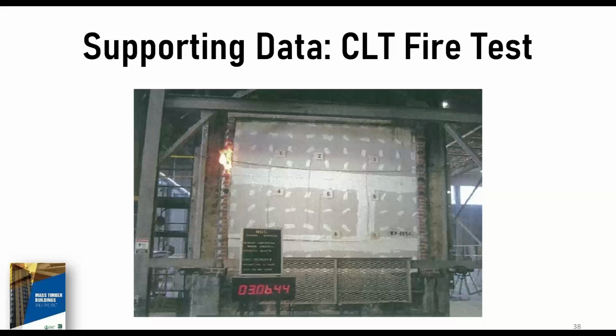The first is a penetration, flame front penetration of the assembly. You can see in our picture here we have a little flame licking out from the upper left corner of the wall assembly. Or your interior wall assembly temperature gets too high. That's typically measured with thermocouples that are installed in the wall to make sure that the interior of the wall assembly does not get too hot. Steel and concrete are affected by elevated temperatures negatively, just like wood is. Steel loses its heat treatment fairly rapidly if it's unprotected.